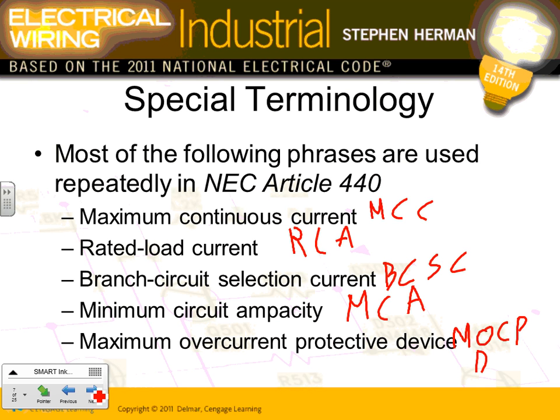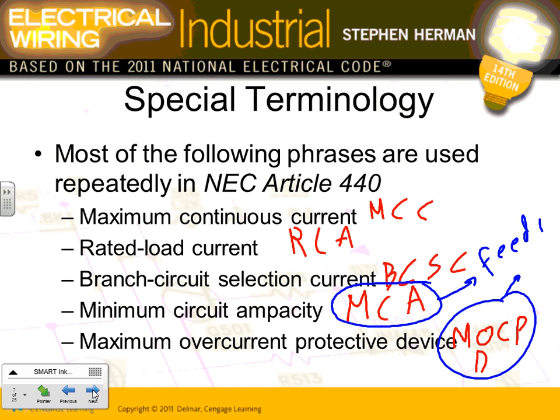Let me go over this, I know we did a bunch of projects. The most important one, guys, you're going to encounter is this one. The minimum circuit ampacity, this is sizing the feeder. The maximum overcurrent device, this is sizing the overcurrent protection device. Can I have everybody's thumbs up in chat, so I know they understand that? Minimum circuit ampacity sizes the conductor, maximum overcurrent device sizes the overcurrent device.